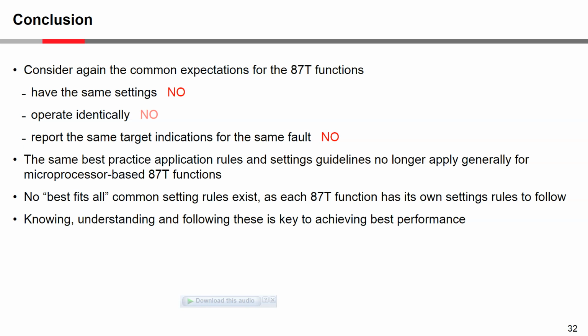Thank you, Mike. And the last question for today: 87T is primary protection. Is it really necessary to apply duplicate 87T from a different vendor when other backup protections are applied? That's really the decision of the protection philosophy of the utility. But normally when you get to transmission level sizes, that is done because when you have an internal fault, particularly, the zone of protection actually extends a little bit outside the transformer as well. But if you have an internal fault, the sooner you get that fault cleared, the better. Because the transformer is a very expensive device, so the more you limit the damage, the better. But that's not the only reason.